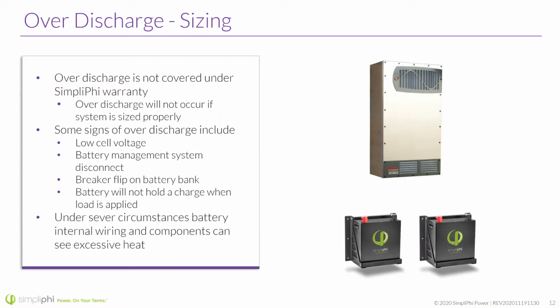Some signs of over discharge include low cell voltage. So the battery might be showing low voltage. This is a kind of tricky one. Let's say we have a 48 volt battery and it's showing 45 volts. That's a different issue. If it's showing, let's say, 20 or 30 volts, or maybe even 2 volts, that could be an indication of low cell voltage. Not always. It might be that the battery management system has gone into a protective state and caught the issue before it actually became a really big, significant problem.